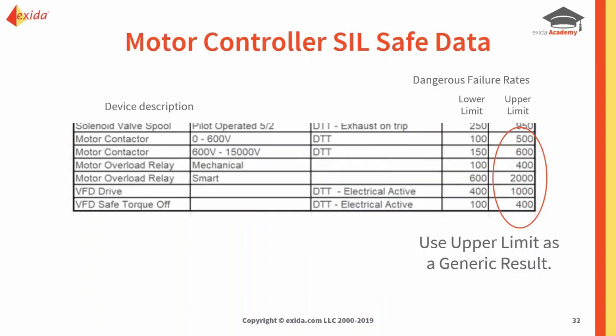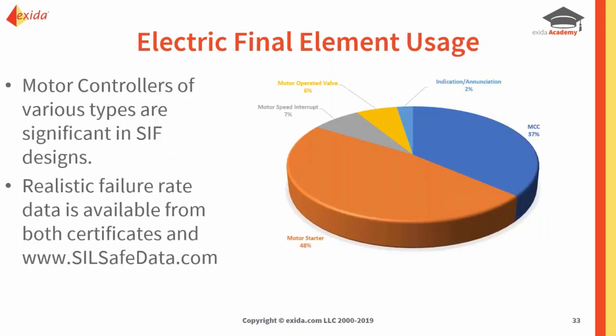Here's a snapshot of SIL Safe Data for motor controllers. It's important to note — and not surprising — that just like with valves, all motor controllers are not created equal; they have different sets of values depending on voltage differences, whether it's a smart device or mechanical device. You can see the motor overload relay has different values — mechanical versus smart — with different lower and upper limits. If you have a mechanical motor overload relay and no other failure rates, this gives you the dangerous undetected failure range — for example, between 100 and 400. It's a great sanity check tool.